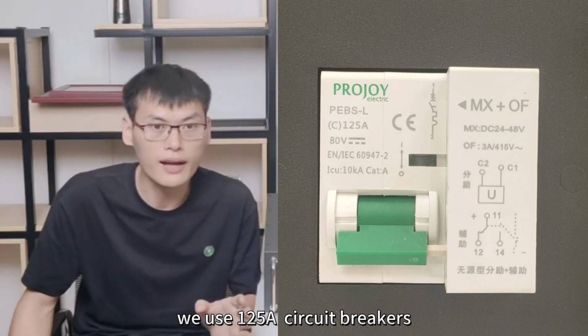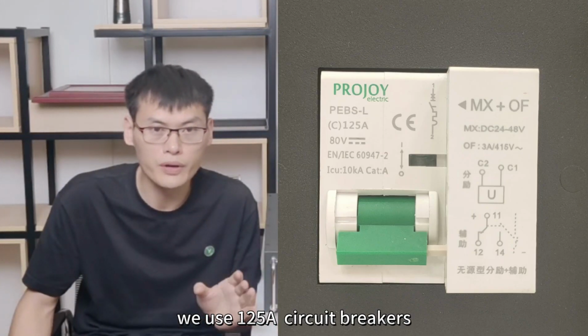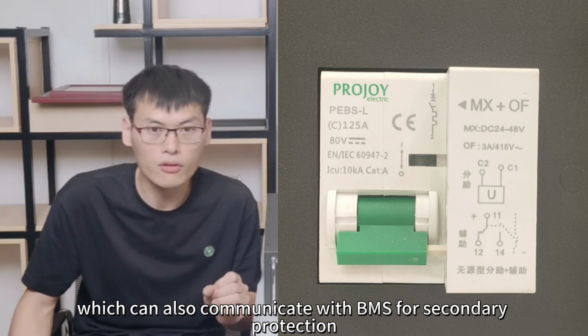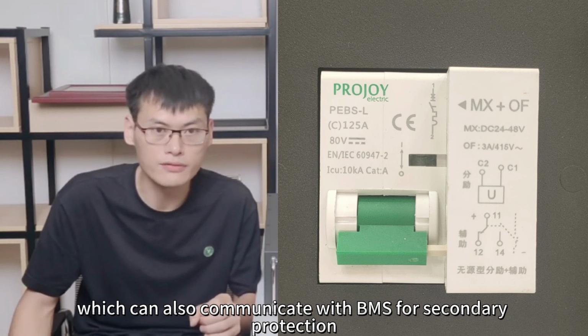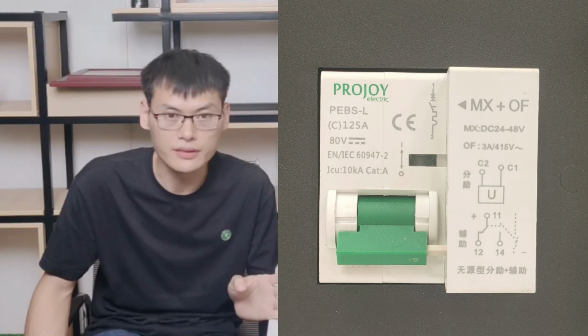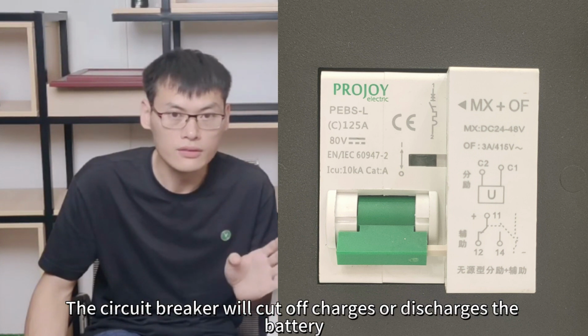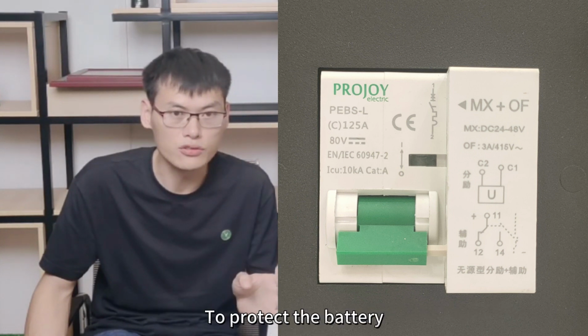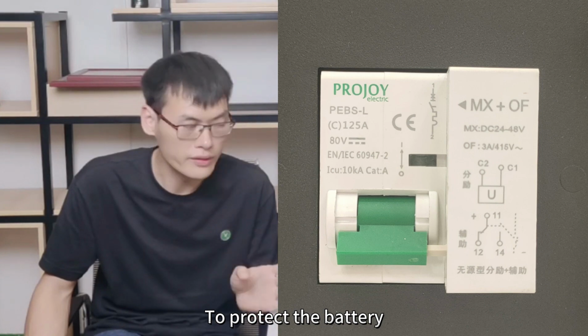We use 125 ampere circuit breakers, which can also communicate with the BMS. When the BMS fails, the circuit breaker will cut off charging and discharging of the battery to protect it.